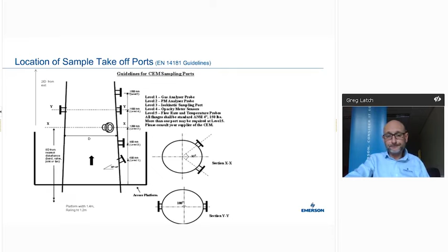Okay, and not to be obviously forgotten, from an EPA exhausting aspect or release, you do need to know your stack flow rates. You can use things like annubars, for example, using multivariable flow meters for compensation with pressure and temperature. And that detail is very handy, obviously, to have to give you your load mass balancing as well for your plant. Not to mention then to time and date stamp your rate of emission and what sort of excursions you may have had at any particular moment.